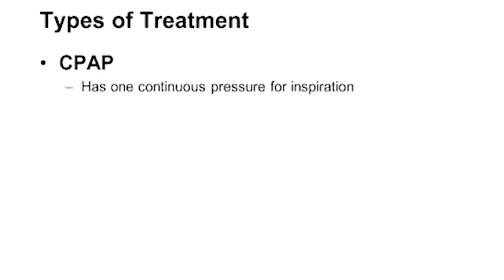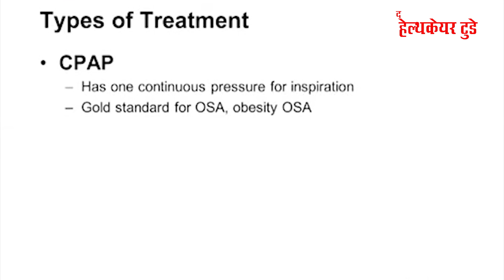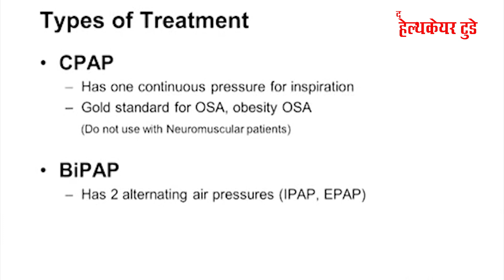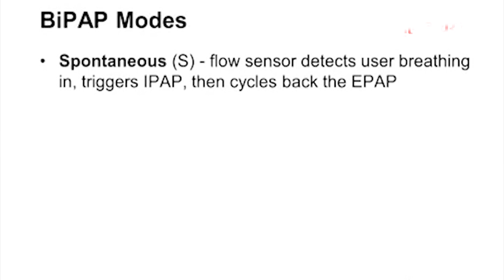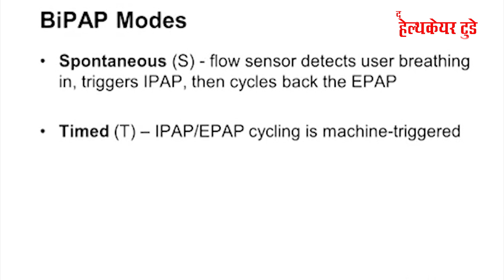Types of treatment. CPAP has one continuous pressure for inspiration. It is the gold standard for OSA and obesity OSA. Do not use with neuromuscular patients. BiPAP has two alternating air pressures, IPAP and EPAP, and is available in 3 modes. Spontaneous is when the flow sensor detects the user breathing in and triggers the IPAP, and then cycles back to the EPAP. Timed is when the IPAP and EPAP cycling is machine-triggered.